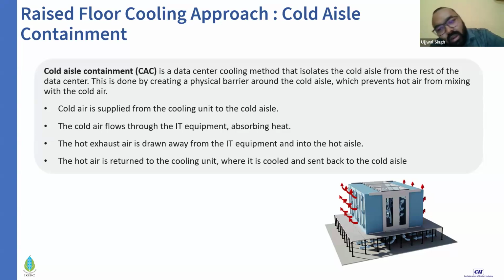So when we say cold aisle containment, I have a PAHU located at a distant place in a mechanical gallery, supplying cool air to the plenum, that is, the false flooring. From there, cold air comes inside, as you can see with these blue arrows, into a contained zone that fills up with cold air. Servers on both sides suck up this air through IT fans, which push the hot air back, and it gets collected in the false roof or false ceiling and is sent back to the PAHU for cooling. That is cold air containment in a crux.